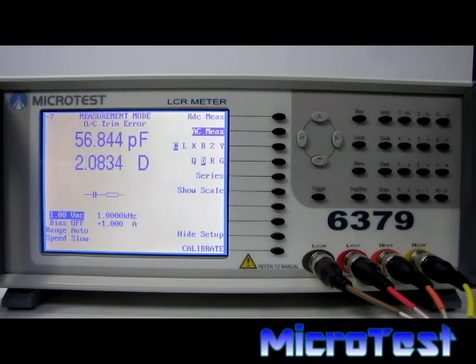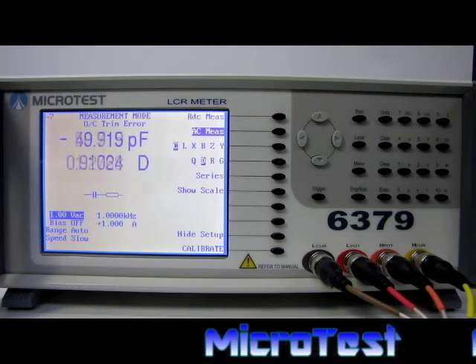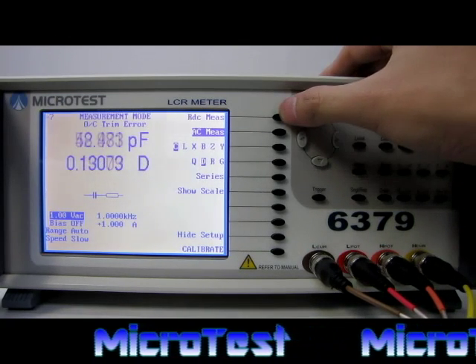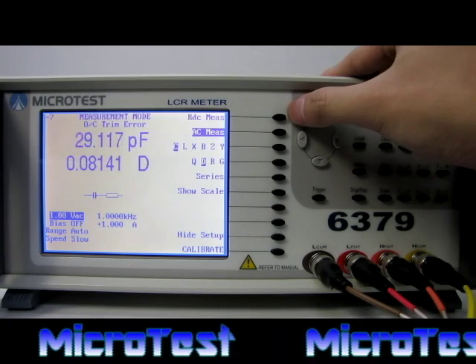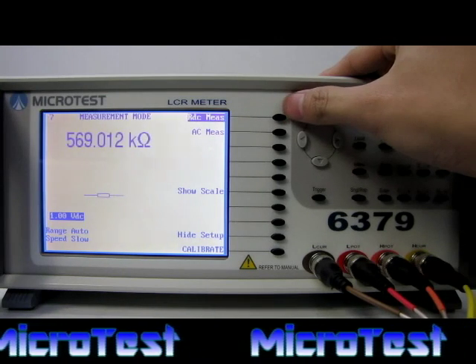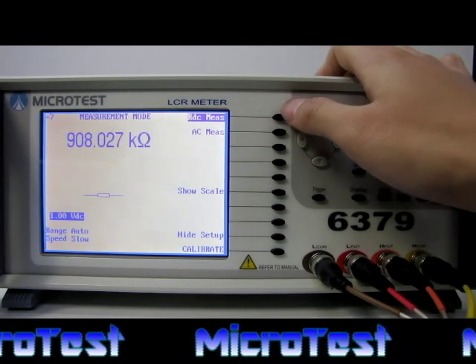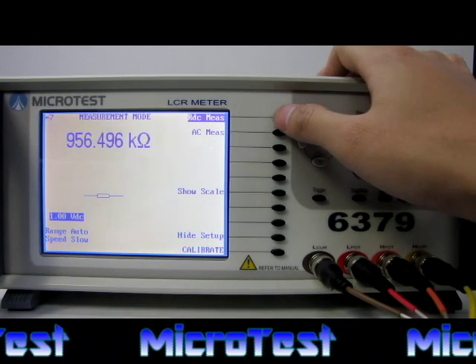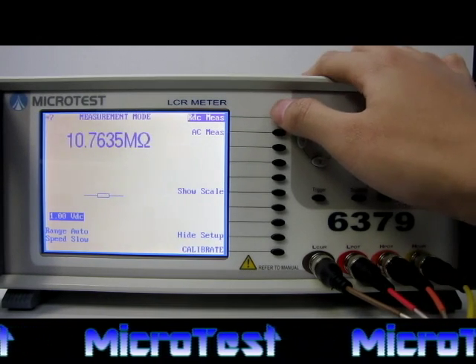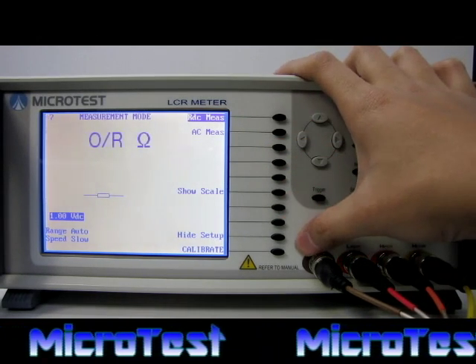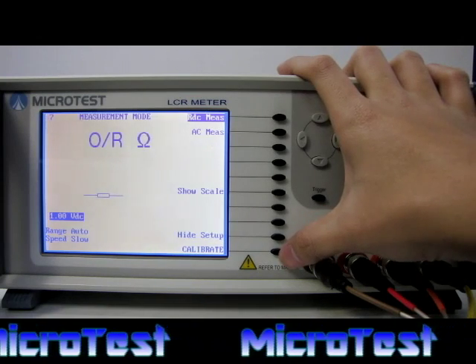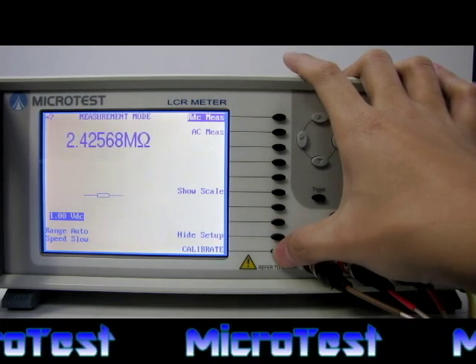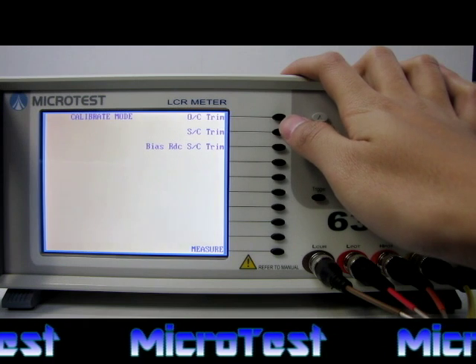How to perform RDC tests. On the top right of the main screen, there is RDC Meas. Press S1 to enter. It is recommended to calibrate first before any RDC test. Press S10 for calibration and to enter calibration mode.